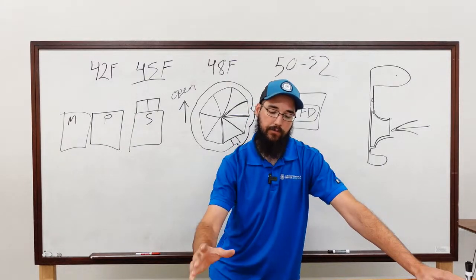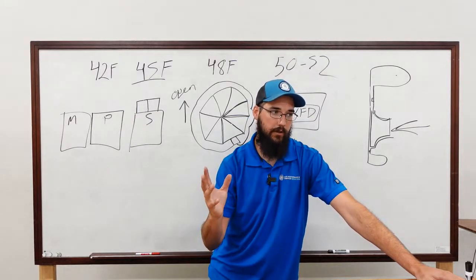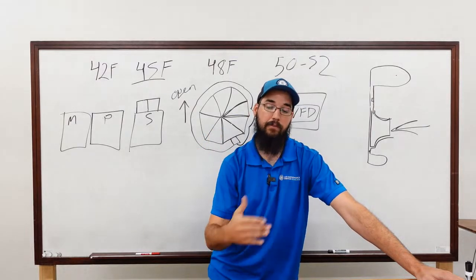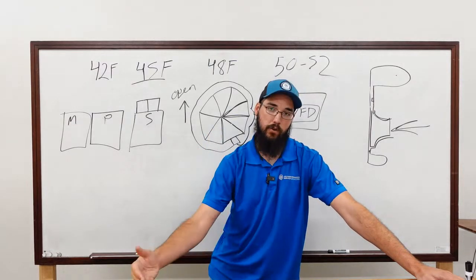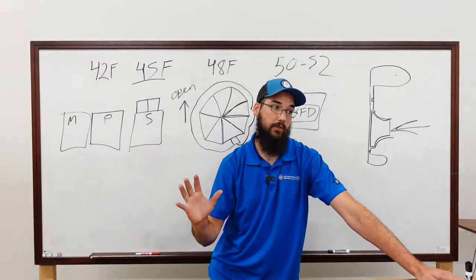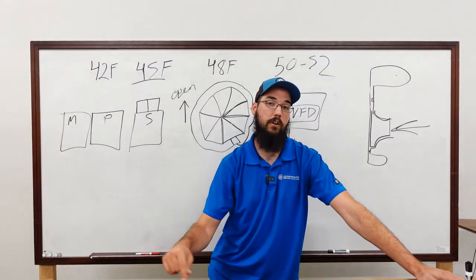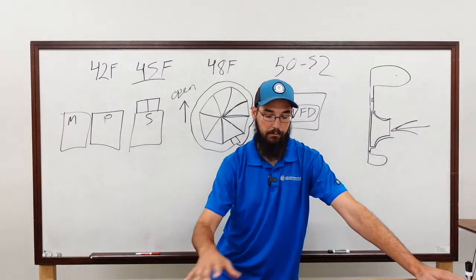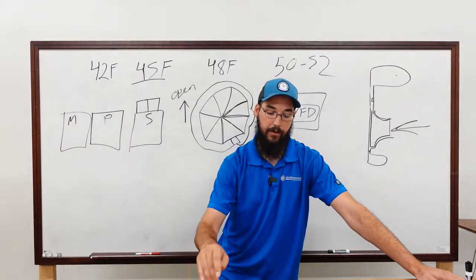instead of flowing water, you could drain the water. That is an alternative. Some people do it that way. I personally don't. If I have the option in a pump, I'm going to flow water through the barrel. Sometimes that's not an option, legitimately. So if that's not an option, get that water out of that barrel. Don't let any water stand in there on both of them. Just play it safe. Do the evaporator and the condenser.